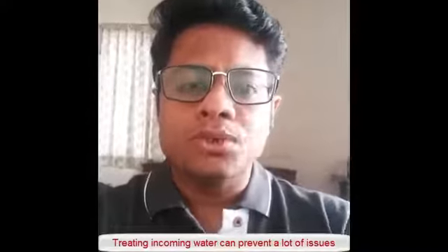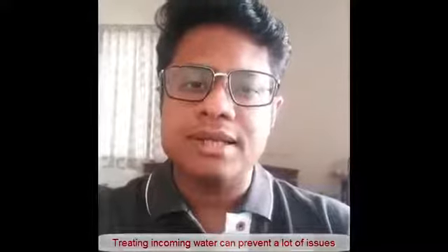When you see two cylinders, the standard ones are a sand filter and a carbon filter, together with a softener sometimes. The first cylinder you generally see is a sand filter, which reduces the turbidity of the incoming water. If the water is not clear, the sand filter will reduce particles and make it a little clearer. They use different grades and sizes of sand so the particles are filtered. However, for higher turbidity, there are different materials available for filtration.